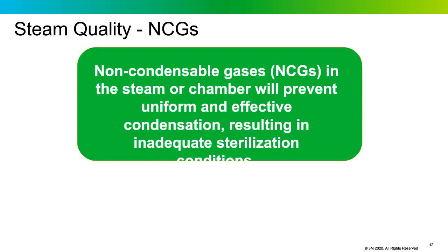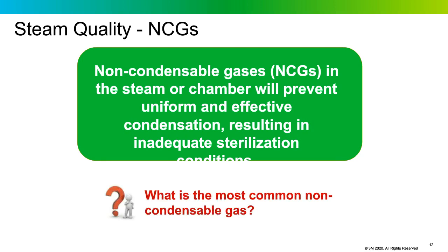Non-condensable gases can prevent uniform and effective condensation of saturated steam, resulting in inadequate sterilization. The most common non-condensable gas is air leaking in. Potential sources include inadequate air removal in the sterilizer, air leaking through valves or gaskets, gases trapped in the supplied steam, or boiler water that hasn't been adequately de-aerated. Think of air as the enemy of steam sterilization.